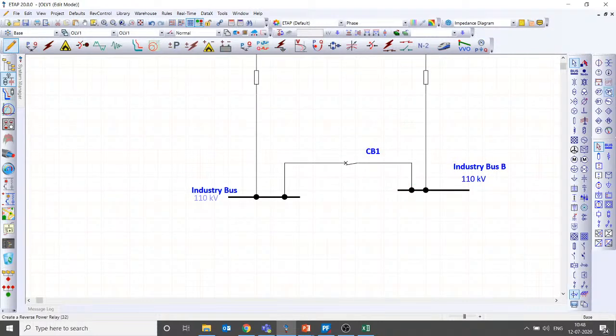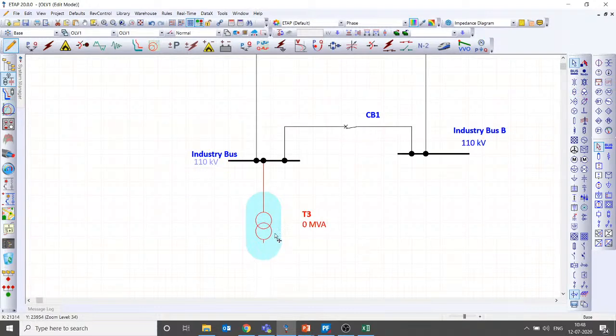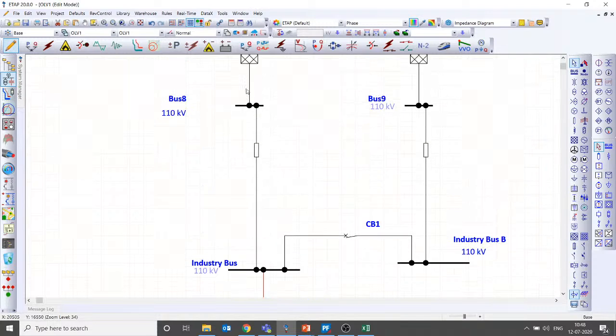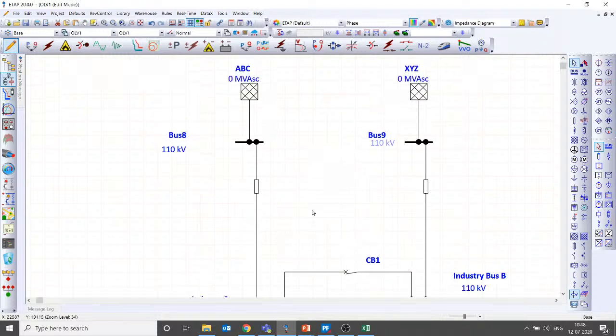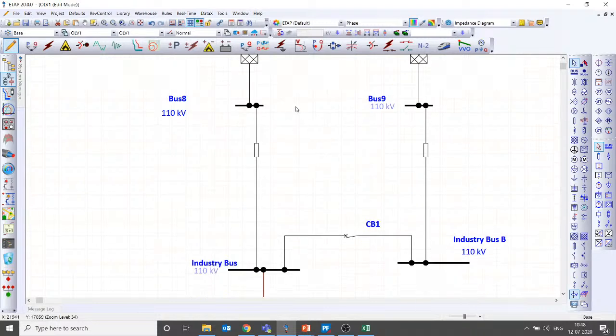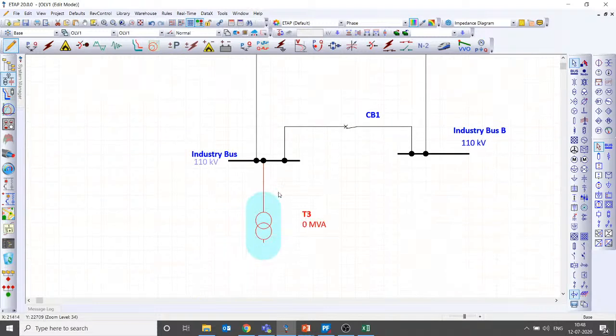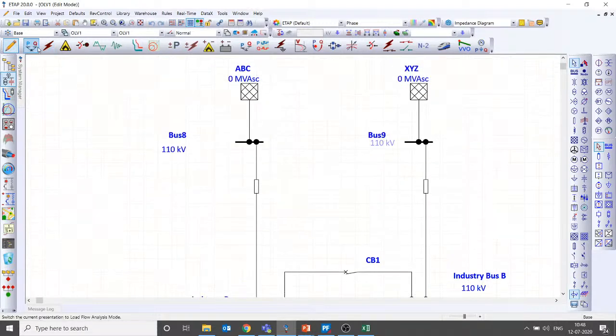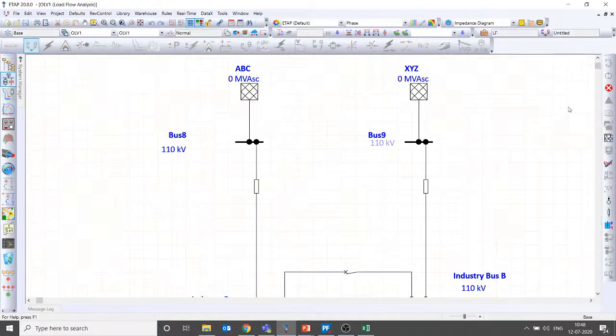That means in an industry you might have further 110 kV to 11 kV step down transformers, and you might be feeding the loads here. But what you have done for your industry, for reliability purposes, is take two different supplies and parallel them at your substation. If the voltage at one substation from where you are receiving power supply is 1 or 2 percent different and the other one is 100 percent, there will be a huge uncontrolled power flow via your industry substation, which is not really allowed.